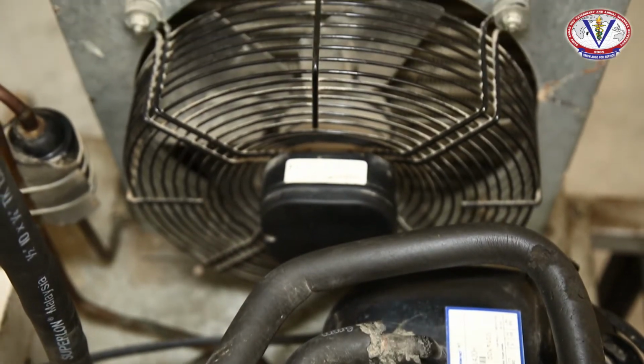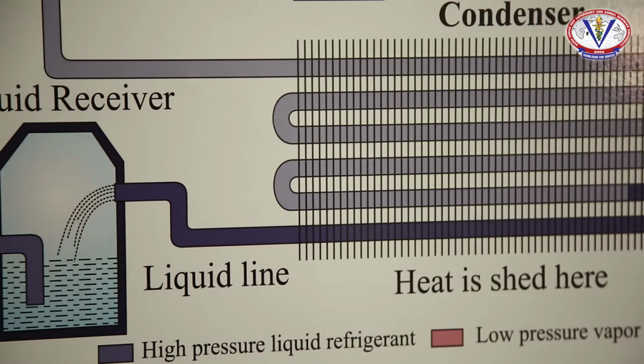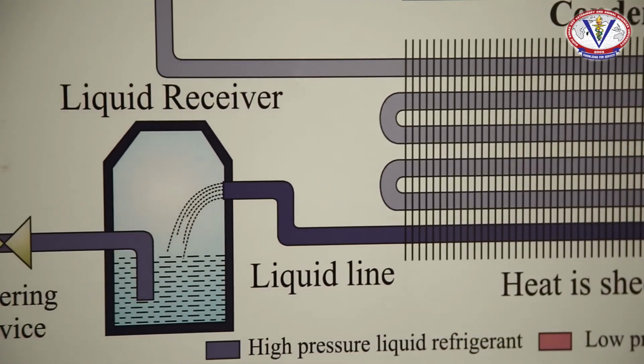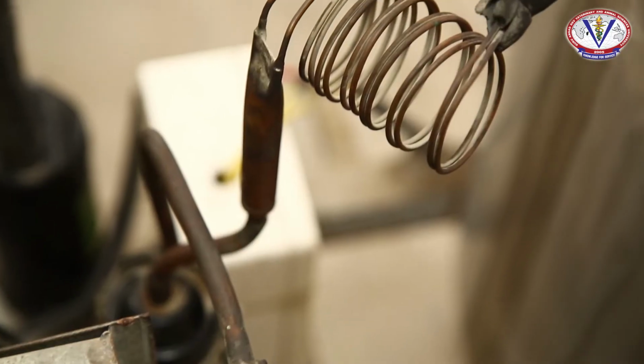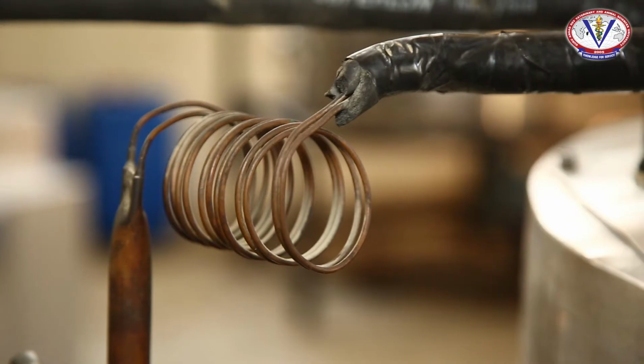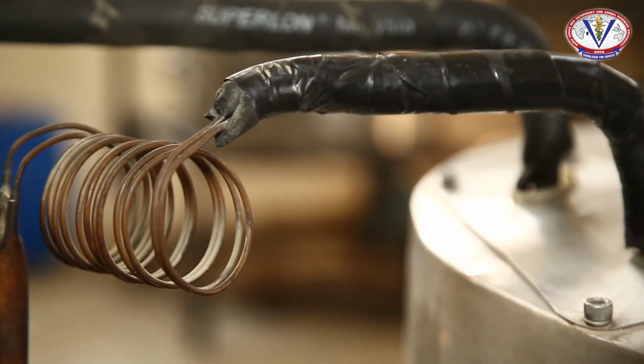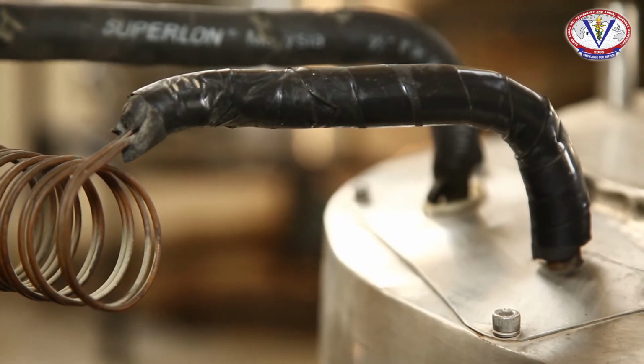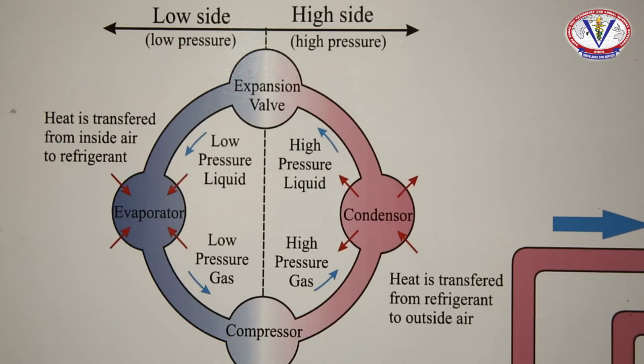so that the vapor refrigerant can be condensed back to liquid form, and this liquid refrigerant is again through a receiver sent to the expansion valve and then to the evaporator. Hence the cycle completes. The refrigeration system works between two pressures, that is low pressure, which is the evaporator side, and the high pressure, which is at the condenser side. Between these two pressures, the vapor compression refrigeration cycle works.